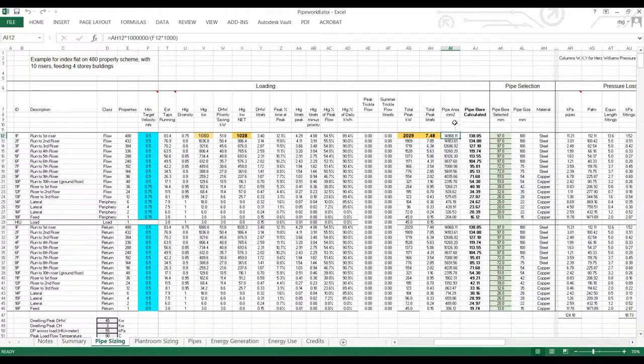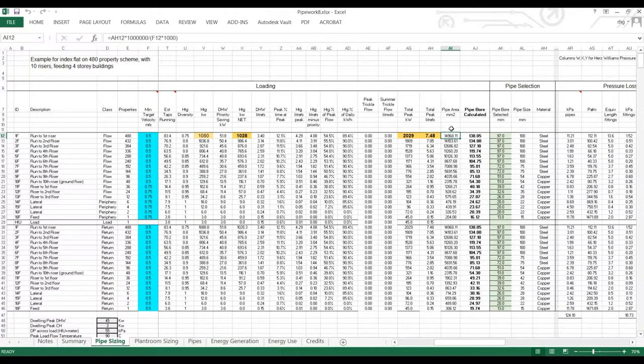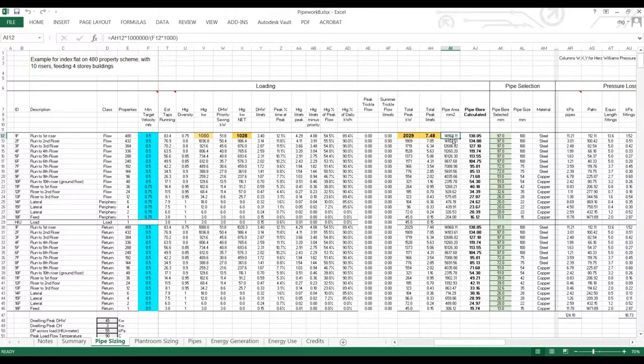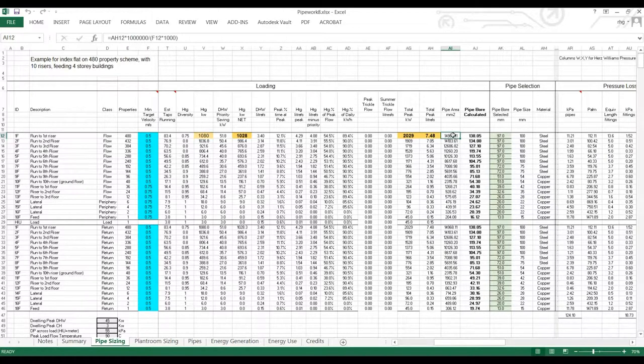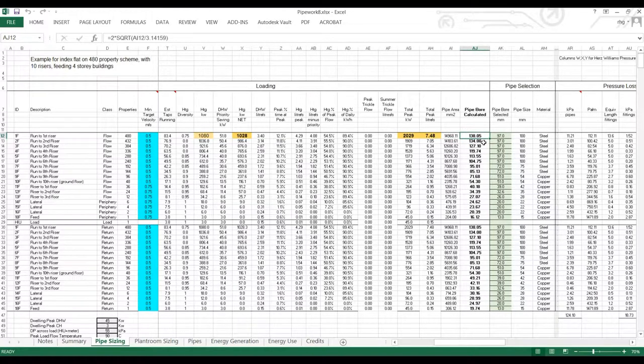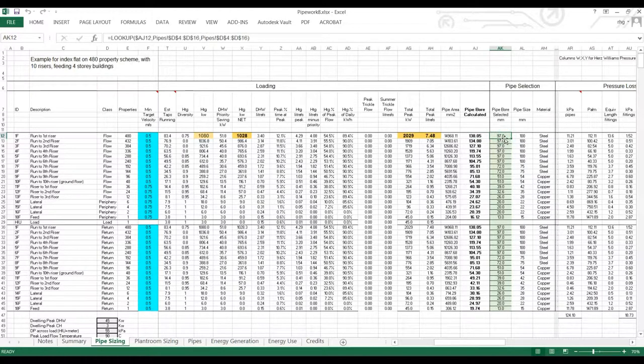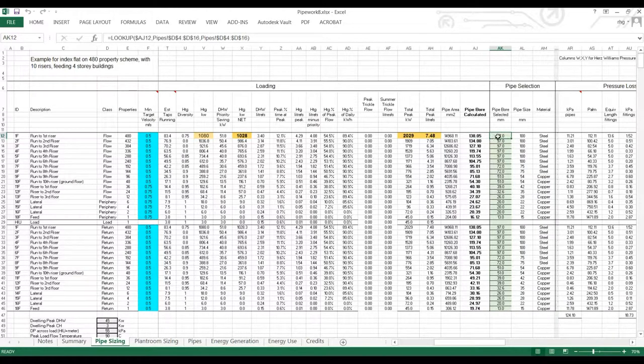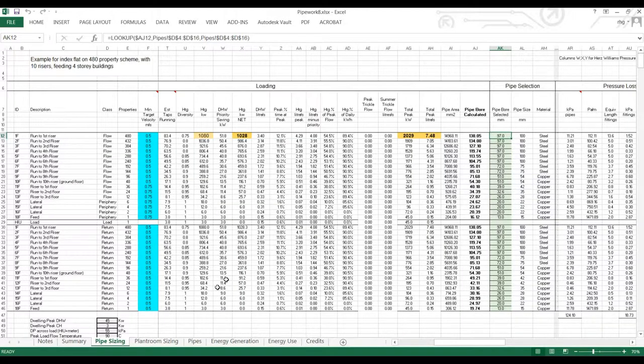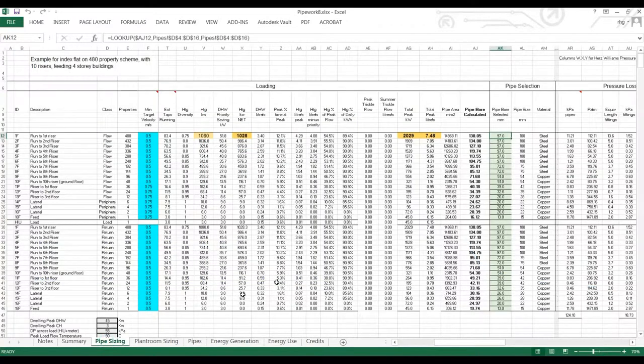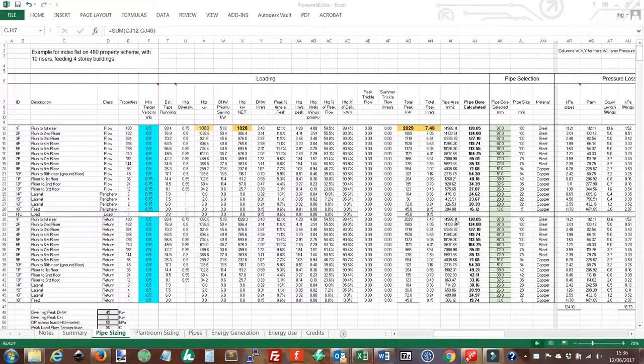Now the pipe area is worked out from the peak flow rates divided by our minimum water velocity. So this gives us a pipe area. From that we can calculate the bore of the pipe. And from there we can get to a selected pipe size. Now these selected pipe sizes come from a table of available pipe sizes that can be amended to suit.